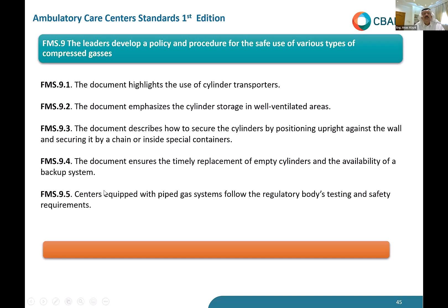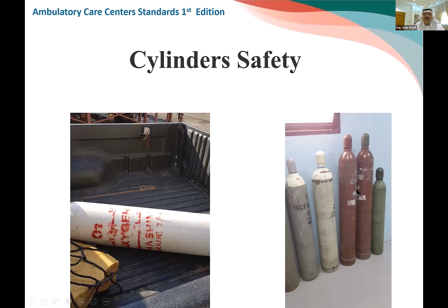The center equipped with a biomedical gas system must follow the regulatory body's testing and safety report. If your center is big and you are using piped medical gas, meaning there is piping, you need to do this. So here are some issues. See, this is bad transportation. There is no chaining on the wall. So this is cylinder safety.